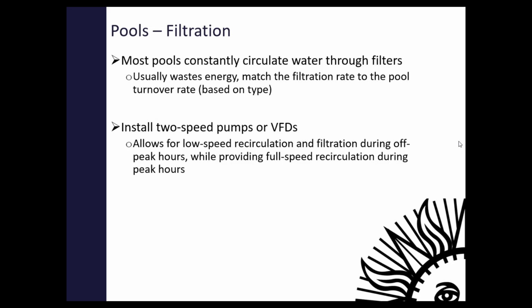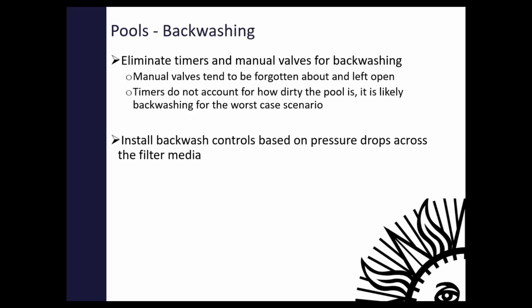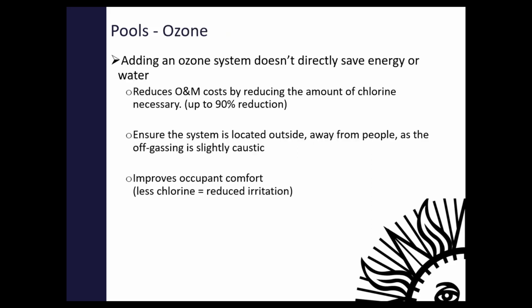And the other thing you can do is figure out what your turnover rate for your pool is. If it's a constant speed pumping scenario, you can reduce the speed of the pump to meet the required turnover for your pool. So I think it's six to 12 cycles per day when it's occupied, and then 2 when it's unoccupied. So that can be something you investigate. Backwashing, I guess this is what I just went over. Just make sure you have something that controls the backwash across your filters.